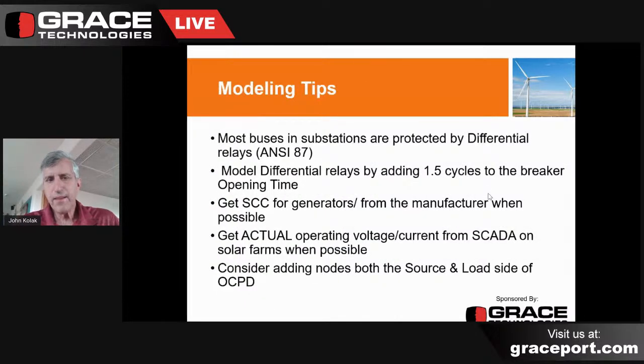So some modeling tips, again, that will sum this up and we'll bring it to closure. As I said, most buses in substations are protected by differential relays. This would be your 87 relays. So when you see an 87 relay, it's a differential relay. Contrast that with an 86 relay, which is a lockout relay. So the 87 relays usually drive the 86 relays, in which case it will operate multiple breakers at the same time. So in a substation, for example, you may have to clear multiple circuits simultaneously, and that's what the 86 relays do. It's essentially clearing each individual device. It gets the trip signal from the differential relay, the 87 relays.